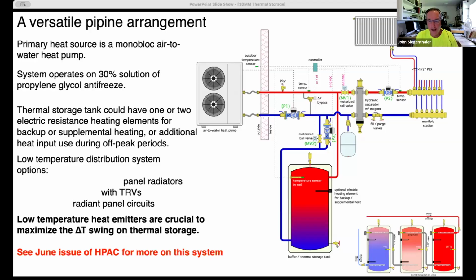Down in the very lower left, I'm showing how you could extend the amount of thermal storage with, in this case, 3 tanks. Those tanks are piped in series with each other, and there's a very specific reason for that. We're trying to maintain good temperature stratification. We want the hottest water in the top of the rightmost tank, the coolest water in the lower left tank. So again, I'd encourage you to go back to the June issue, take a good look at this system, and it walks you through these different operating modes.